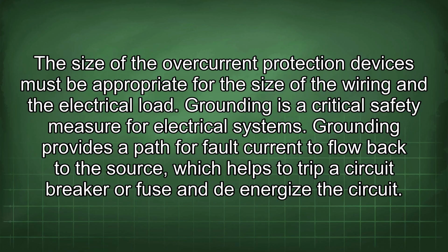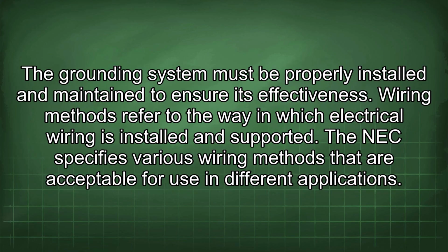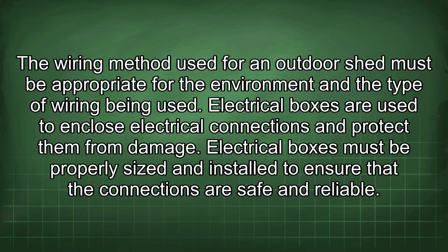Grounding is a critical safety measure for electrical systems. Grounding provides a path for fault current to flow back to the source, which helps to trip a circuit breaker or fuse and to de-energize the circuit. The grounding system must be properly installed and maintained to ensure its effectiveness. Wiring methods refer to the way in which electrical wiring is installed and supported. The NEC specifies various wiring methods that are acceptable for use in different applications. The wiring method used for an outdoor shed must be appropriate for the environment and the type of wiring being used.